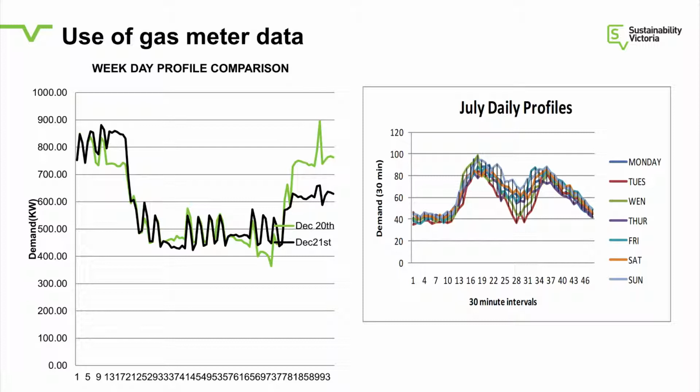What that shows is that on a cluster, a normal week, there's quite a variance in the amount of energy that's being used. You can see that there's quite a range, particularly in the afternoons there, around 28 there. It's when people are going home, but there's a hell of a lot of difference between the highest and the lowest for that month, yet the production's the same. So why? You ask people why. Did guys leave ovens going on one day? On last Wednesday, did they leave the ovens going when normally they switch them off? That sort of graph is fantastic. Really, there shouldn't be much difference from one day to another. If there is, why? There might be a good reason, but at least ask the question.